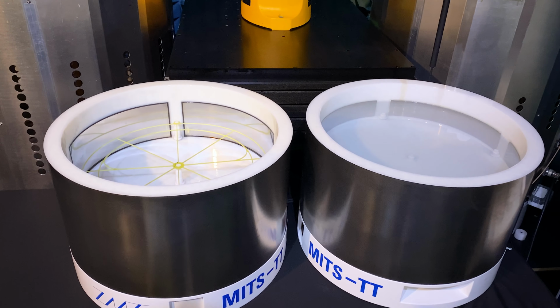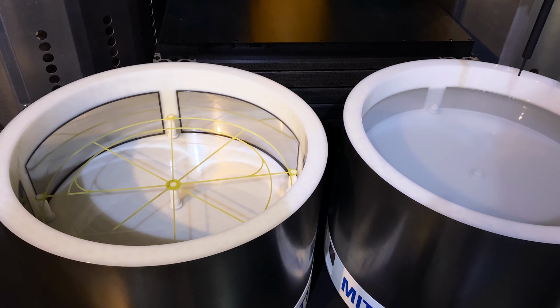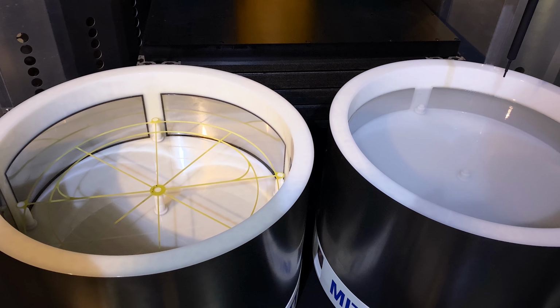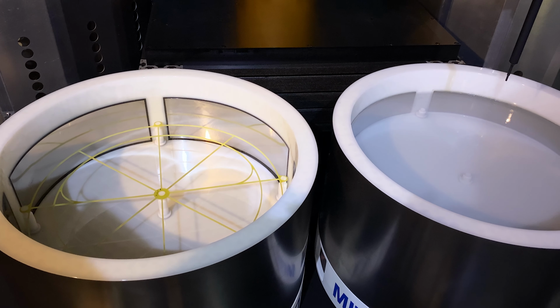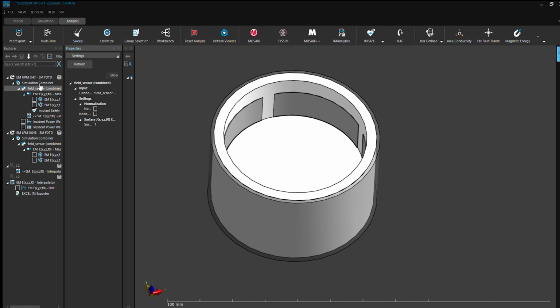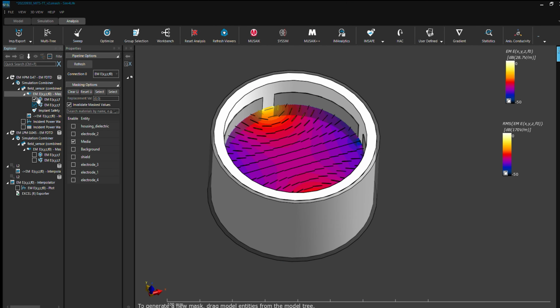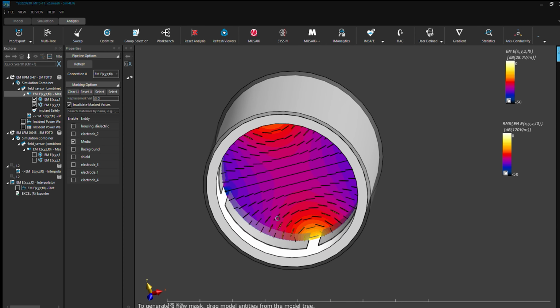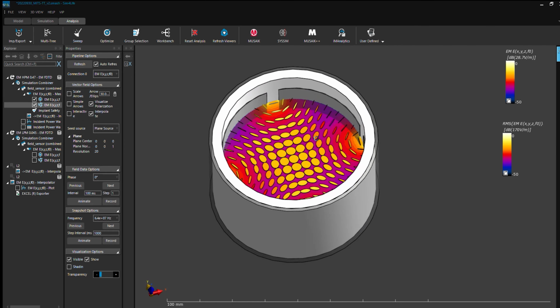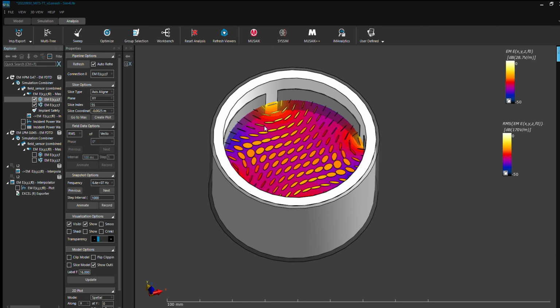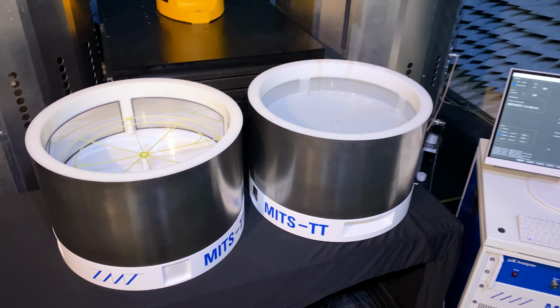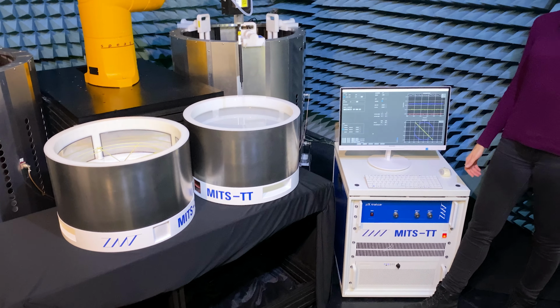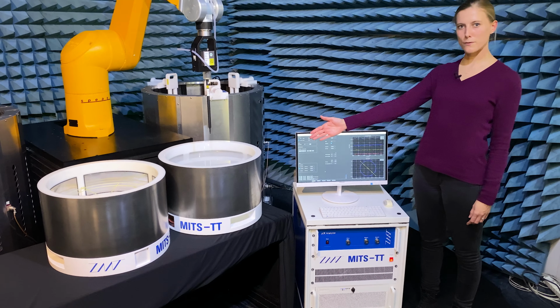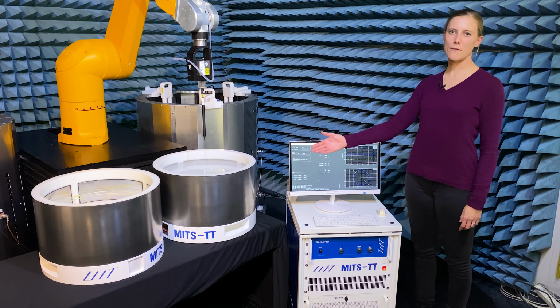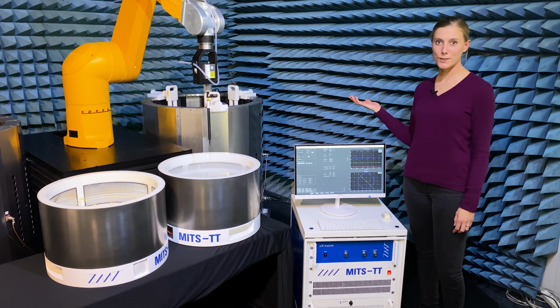The voltages across these 2 electrode pairs are generated by 2-channel amplifiers that operate at 64 and 128 MHz. The relative amplitude and the relative phase between these 2 electrode pairs is controlled by the software, and we can apply any polarization we like, linear, circular, or user-defined. The MITS-TableTop comes with the advantages of higher accuracy. It's small enough to fit on this table, it uses small amplifiers, and we actually don't require the shielded room.